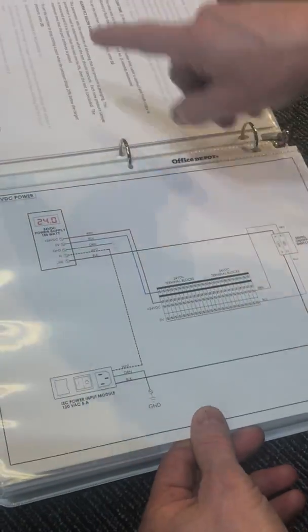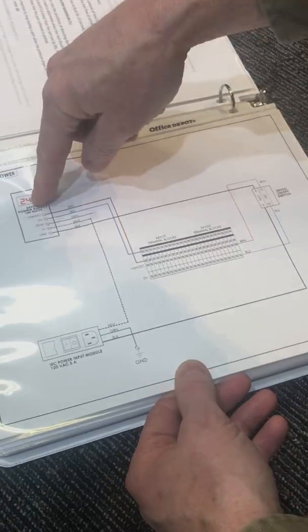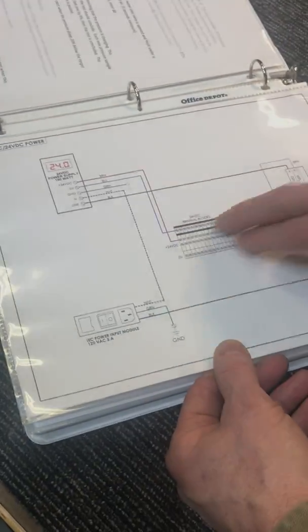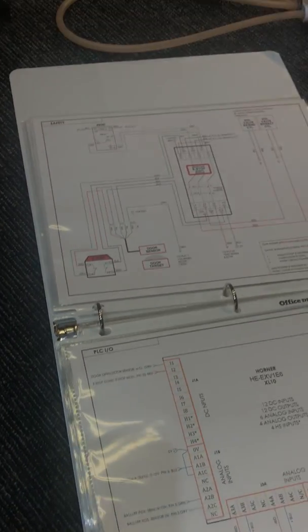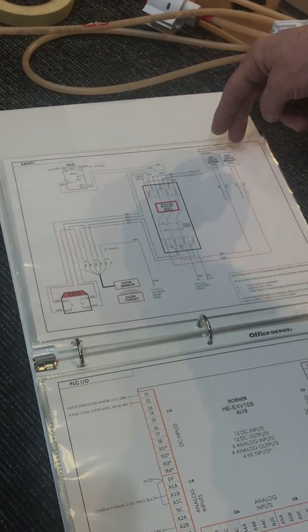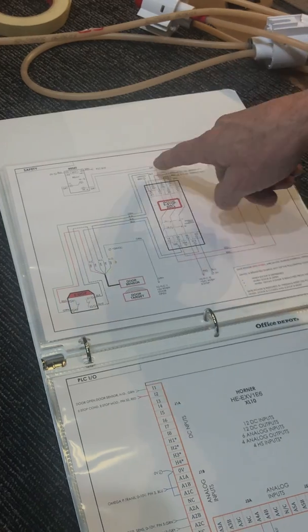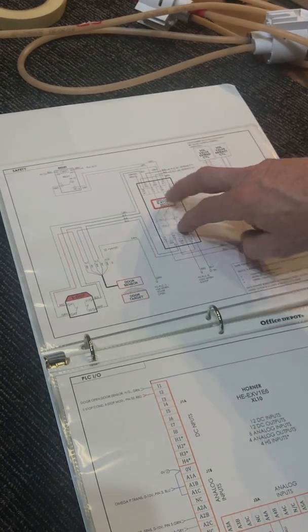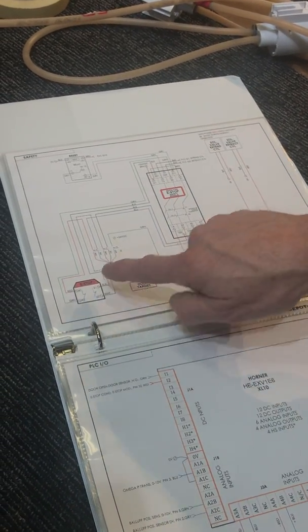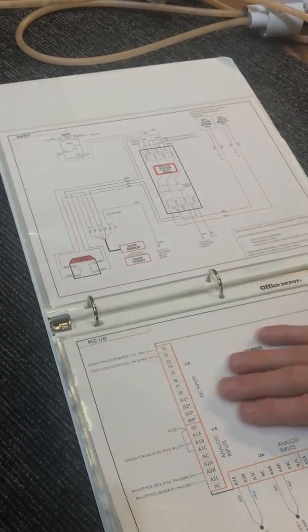Then your schematic. So this is kind of what I just walked you through. Bring in your 120 volts, turns it into 24, and it runs it into these terminal blocks, and then your power on and off switch. This is your safety circuit, so that the valves that you want safe can only get their power when this thing is operating correctly. E-stop and door sensor. This is the PLC. If you looked at that, it looked the same. Absolutely. So the wires are the same, the colors, locations. So that's what your PLC is doing.